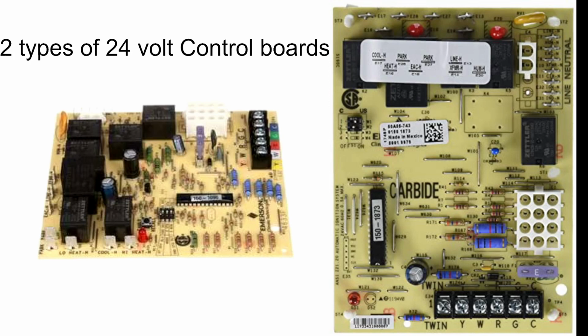If you're receiving 24 volts or 27.2, as we usually see, sometimes 26.8, that tells you that your transformer is actually feeding out into your control board. And we will go over transformers as well in a different video. But this is your wiring setup on how this goes.